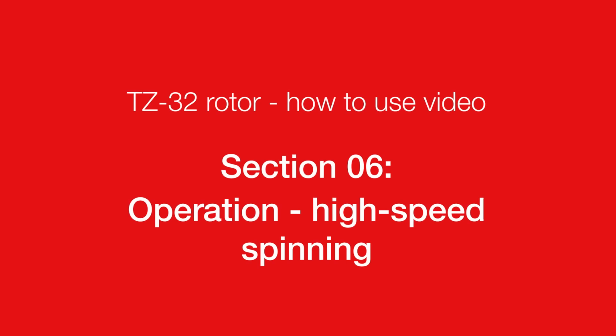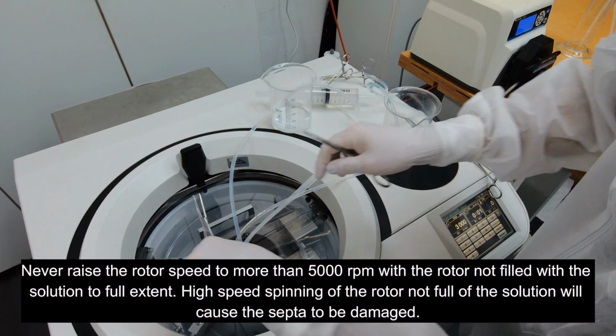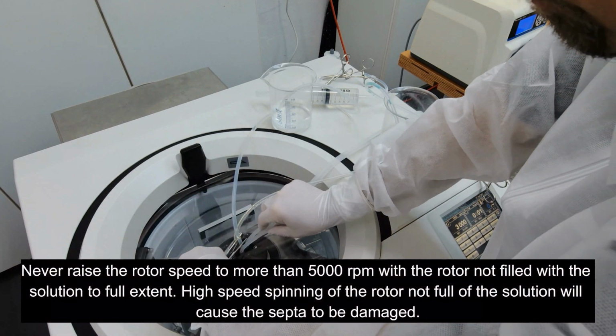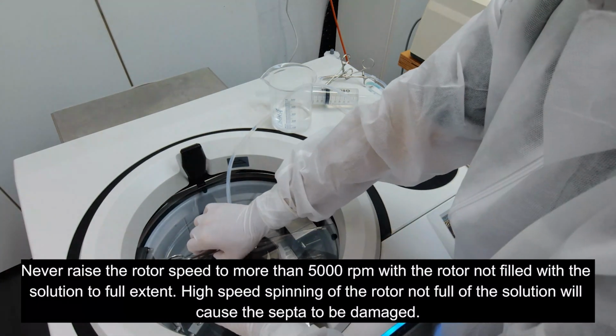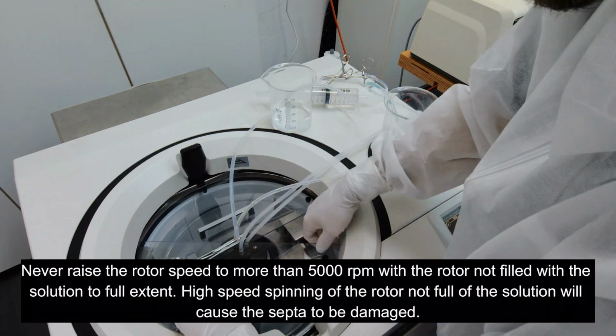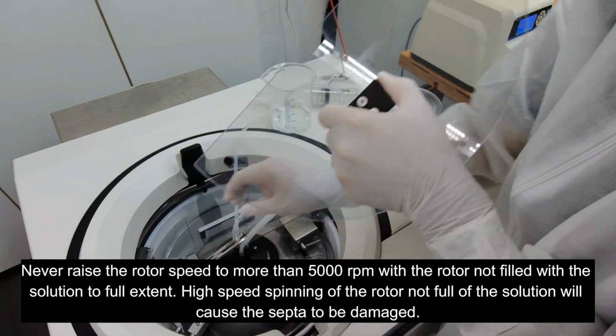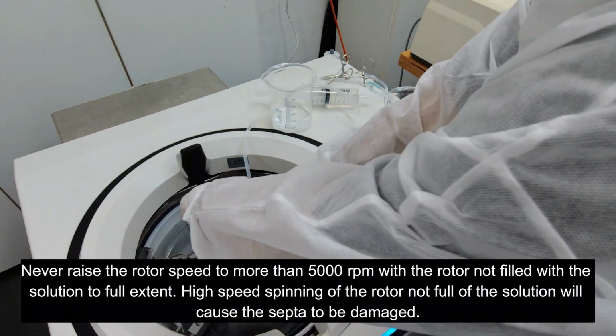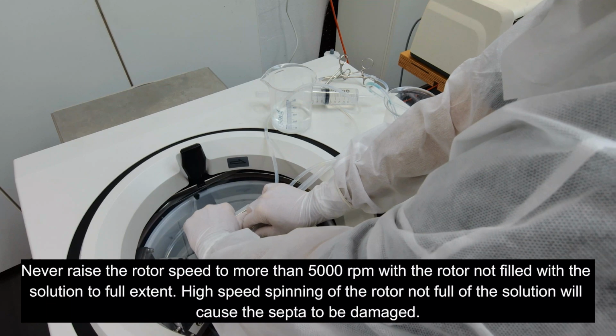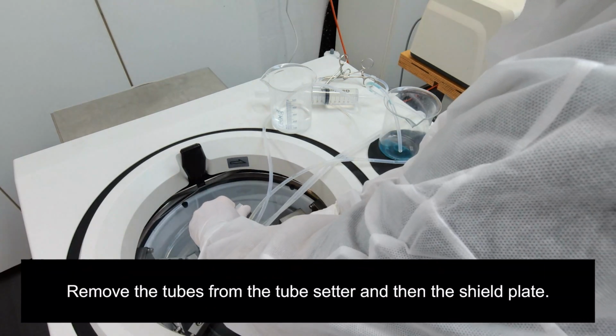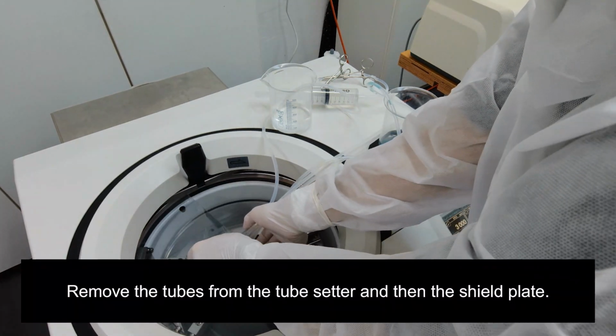How to use video. Section 6. Operation. High-speed spinning. Never raise the rotor speed to more than 5000 rpm with the rotor not filled with the solution to full extent. High-speed spinning of the rotor not full of the solution will cause the septa to be damaged. Remove the tube from the tube setter and then the shield plate.